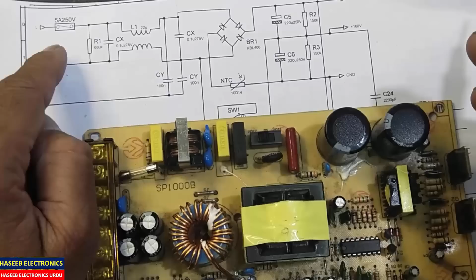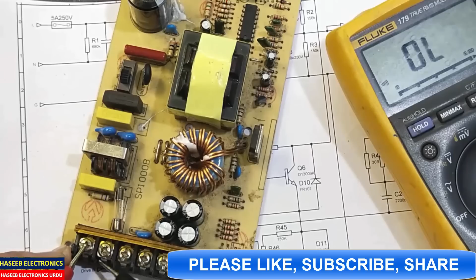This causes the fuse to blow. Most of the time when there is a lightning strike or similar, these capacitors become short circuit. So if there is continuity here, and if we replace a burned fuse but it burns out again with continuity found in this line, we have to check these two components.